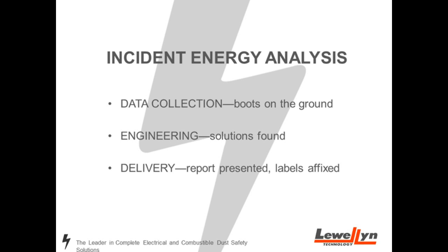The final step is someone has to come back to the facility and apply labels. If you're doing this internally, that's wonderful, but if you're outsourcing it, you need folks on site, on the ground, in your building, helping you get this done. A report is generated from all of this - the arc flash assessment, the incident energy calculations - and then labels need to get put on the cabinet.